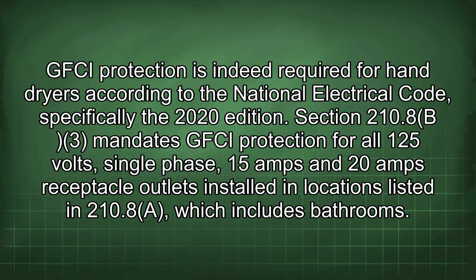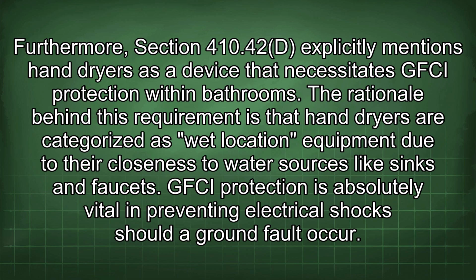GFCI protection is indeed required for hand dryers according to the National Electrical Code, specifically the 2020 edition. Section 210.8(B)(3) mandates GFCI protection for all 125 volts, single-phase, 15 amps and 20 amps receptacle outlets installed in locations listed in 210.8(A), which includes bathrooms. Furthermore, Section 410.42(D) explicitly mentions hand dryers as a device that necessitates GFCI protection within bathrooms.